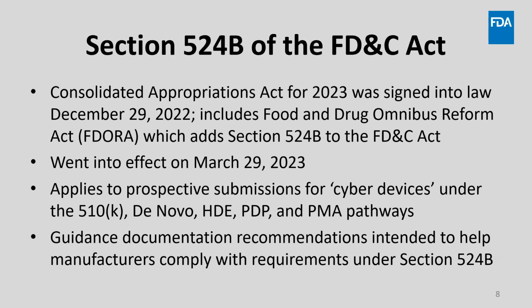These requirements apply to prospective submissions for what are identified as cyber devices under the 510(k), De Novo, Humanitarian Device Exemption, Product Development Protocol, and PMA pathways. As these pertain to the submission pathways, these requirements also apply to special and abbreviated 510(k) applications, as well as PMA and HDE supplements. The guidance documentation recommendations are intended to help manufacturers comply with the requirements under Section 524B.